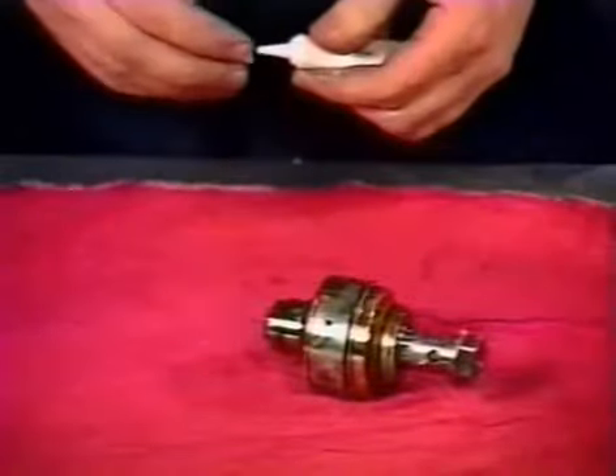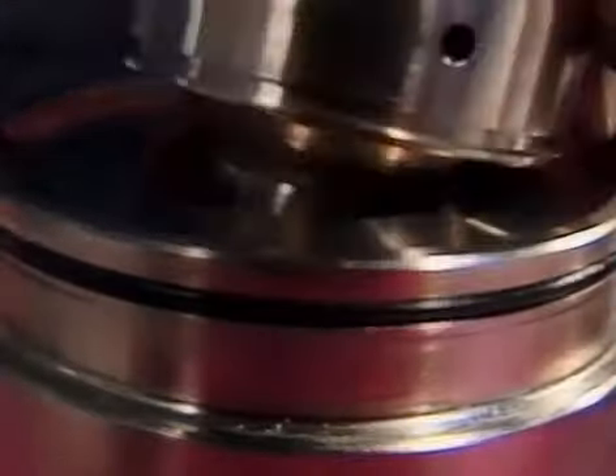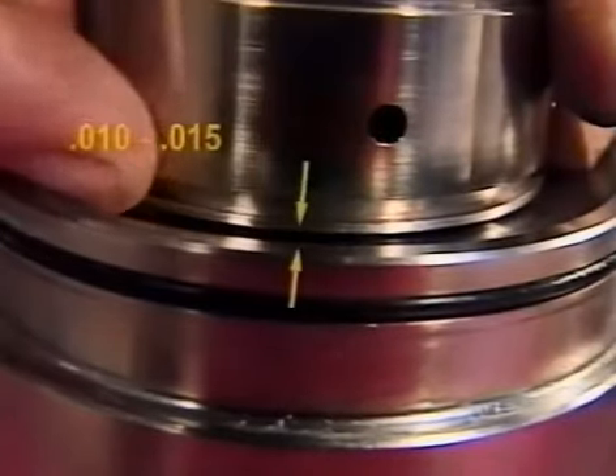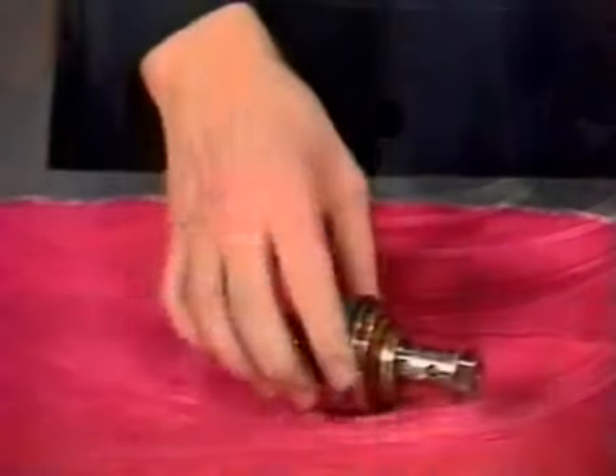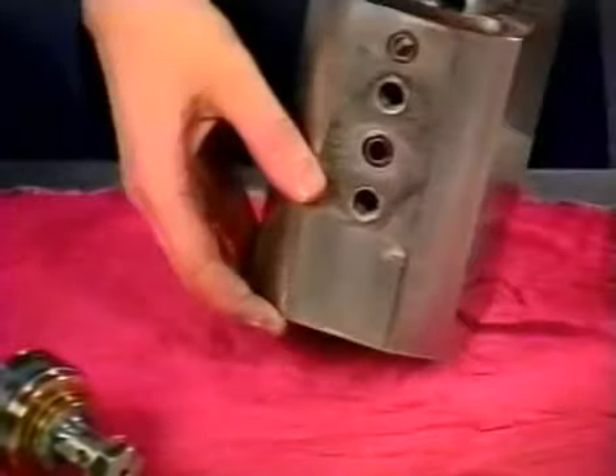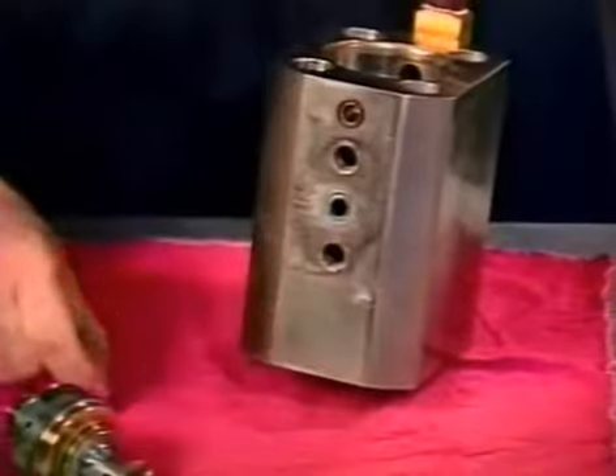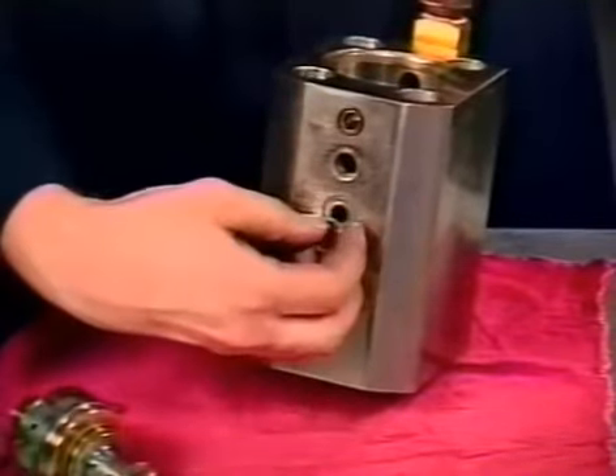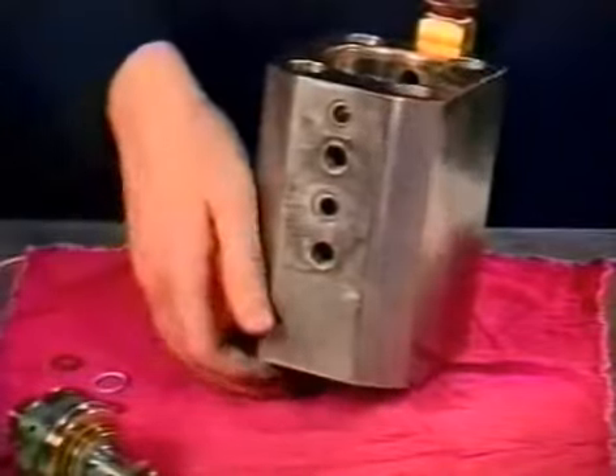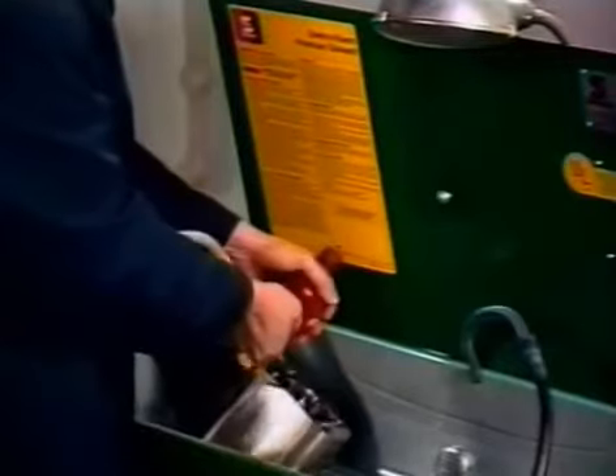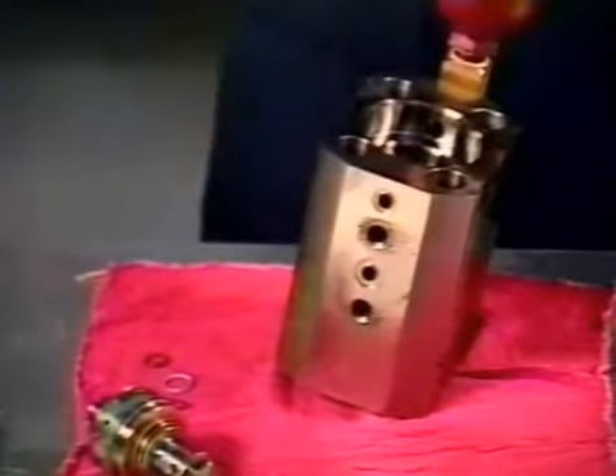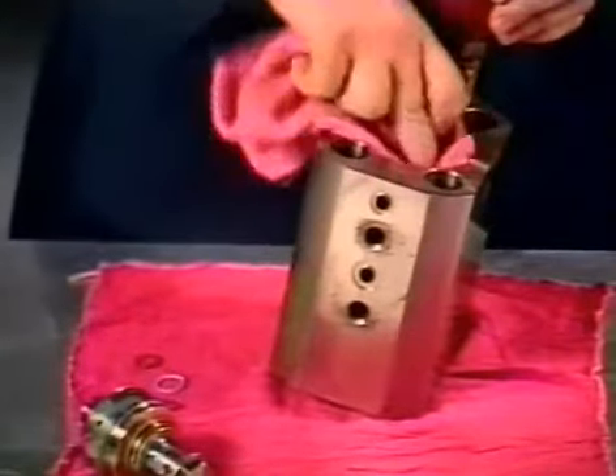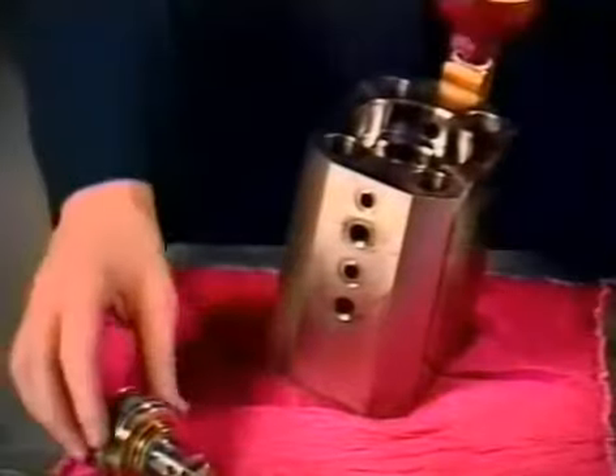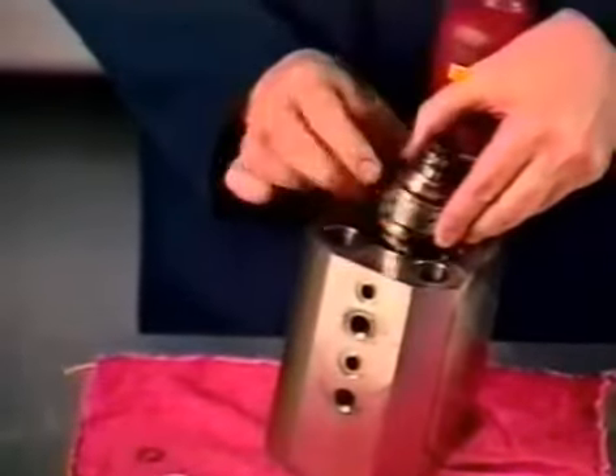Using a high-pressure cylinder and the rebuilt check valve, make sure the check valve and high-pressure cylinder have the correct gap, as described in your operation and service manual. Remove the O-rings and high-pressure seal from the end cap. Clean the end caps with solvent and compressed air. Reinstall the check valves in the end caps as well as the O-rings and high-pressure seals, or replace if necessary.